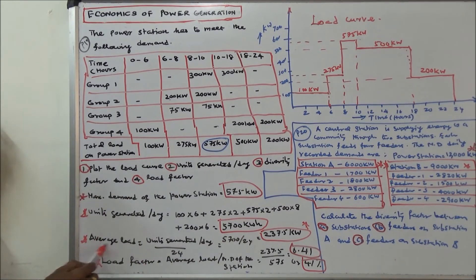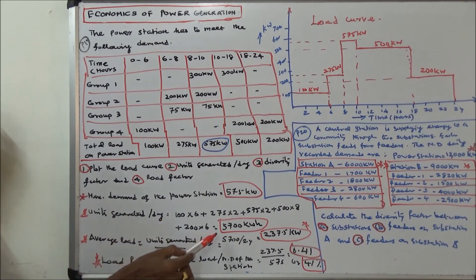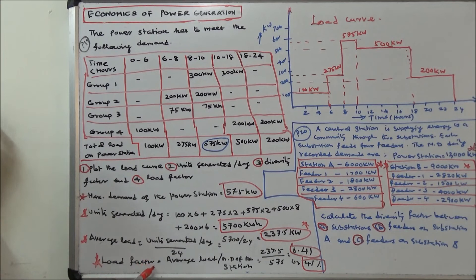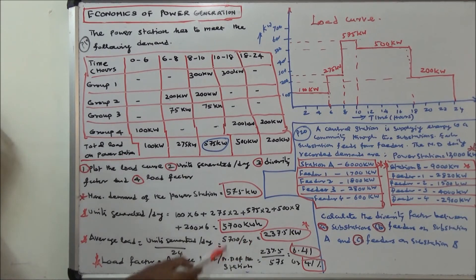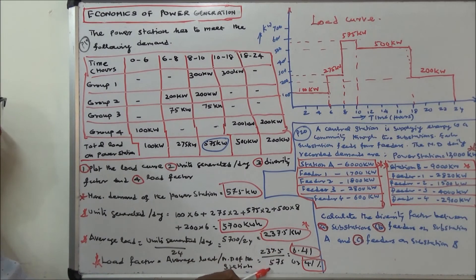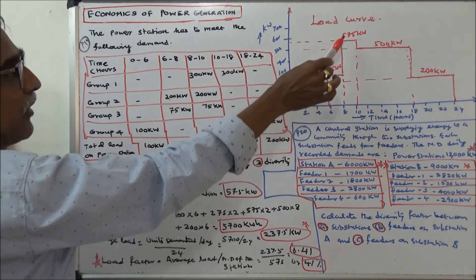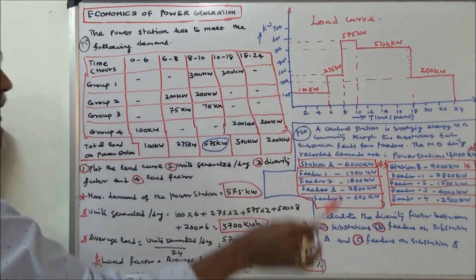Average load equals units generated per day divided by 24: 5700 ÷ 24 = 237.5 kW. Load factor equals average load divided by maximum demand: 237.5 ÷ 575 = 0.41 or 41%. The load curve shows: 100 kW, 275 kW, 575 kW, 500 kW, and 200 kW at the respective time intervals.